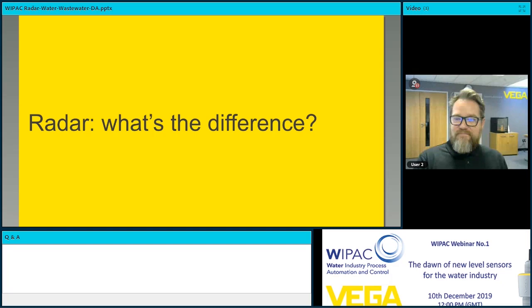And then we had filling into dead bands, causing level echoes to be lost, and we'll cover dead bands a little bit later. And then getting outputs falsely jumping down or resulting in overfills occurring. That was happening with our sensors. And then we saw issues of build-up and condensation on sensors in different applications, whether that was loss of echo from dusty conditions, very heavy turbulence, false echoes, temperature limitations and temperature measurement errors. And we saw crosstalk issues when we wanted to make multi-sensor measurements on solids applications.